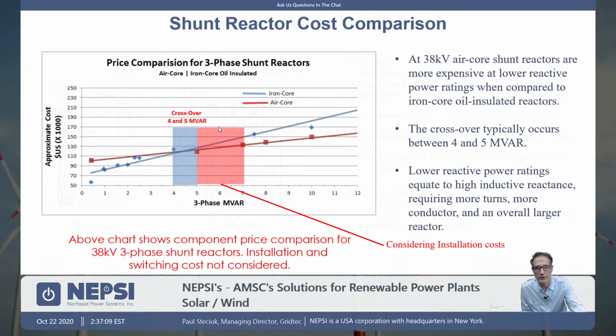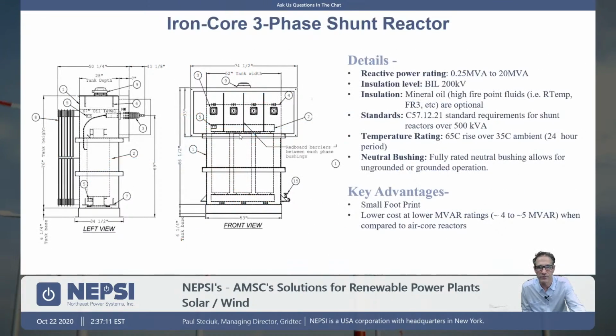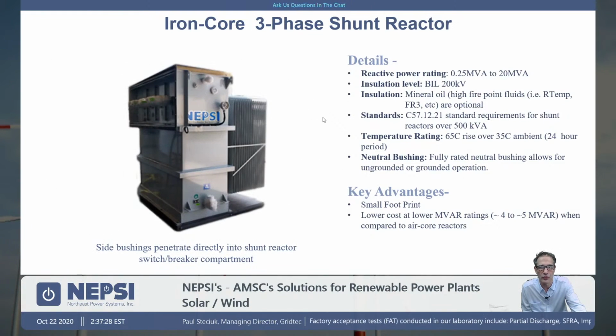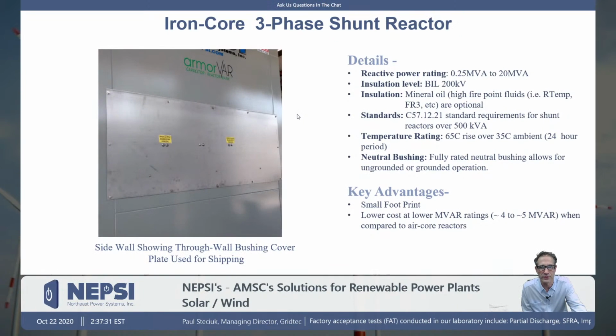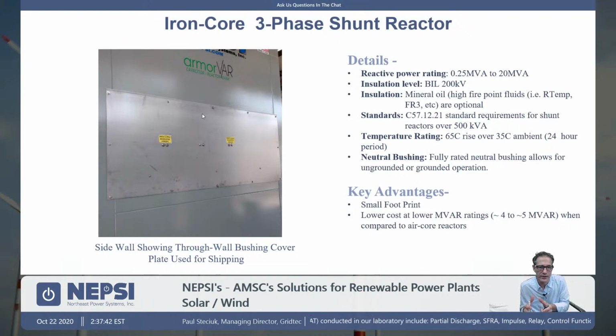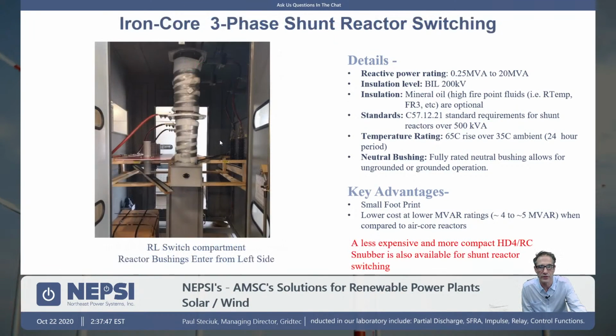So iron core reactors is something to think about, and we're just going to flip through some pictures real quick. These are the typical drawings, and the reactive power rating typically is about 0.25 MVAR up through about 20 MVAR. So we'll include all the switching, protection, and control when these reactors are equipped on the side of our unit. Basically, we have to ship these things separate. Here you can see we have a plate that we've installed, and we remove that plate, slide the reactor up against it, and the connections are made.